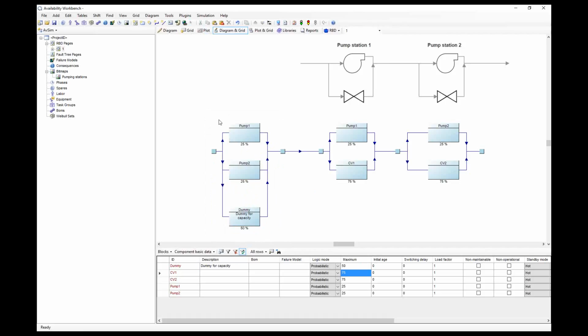The problem here is my availability model, because I still need my check valves. I still need the pumps and the check valves in parallel with each other for the availability model, right? If both the pump and the check valve fail in one pumping station. The problem here is that this availability model is interfering with the capacity model. If I lose this check valve, my throughput through the remaining pump drops to 25%. But that's not how the system behaves in real life. If I lose my check valve, the system can still operate at 100%, so long as the flow continues through both operational pumps. You can lose the check valves and they can be offline and still have 100% capacity. So my availability model is interfering with my capacity model.